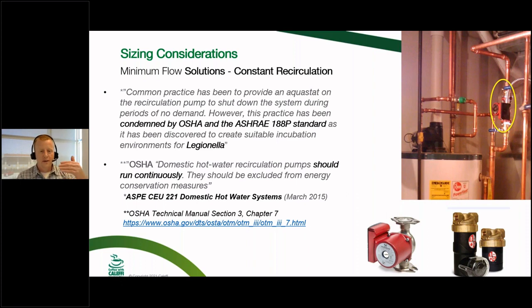Even just a couple of notes here too: we all know that building code requirements are based on occupant safety first and foremost, and then you start talking about energy savings. But in all reality, occupant safety is going to trump energy savings any day of the week. So much so that OSHA has actually come out and condemned the use of aquastats on domestic hot water recirc, citing ASHRAE 188, which is a standard on Legionellosis risk management.